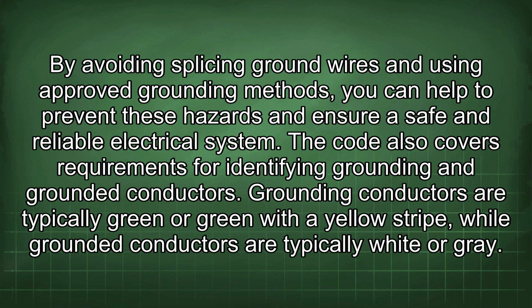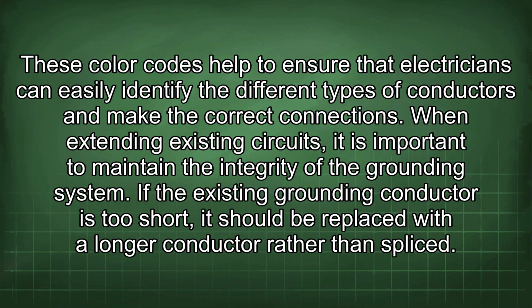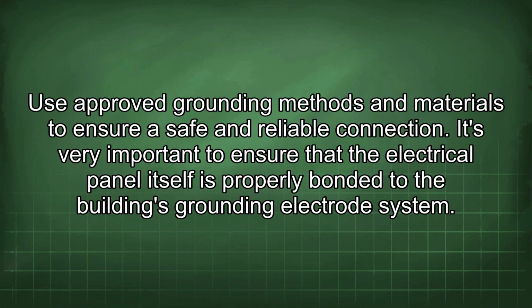The code also covers requirements for identifying grounding and grounded conductors. Grounding conductors are typically green or green with a yellow stripe, while grounded conductors are typically white or gray. These color codes help to ensure that electricians can easily identify the different types of conductors and make the correct connections. When extending existing circuits, it is important to maintain the integrity of the grounding system. If the existing grounding conductor is too short, it should be replaced with a longer conductor rather than spliced. Use approved grounding methods and materials to ensure a safe and reliable connection.